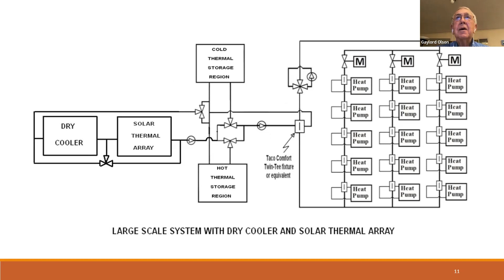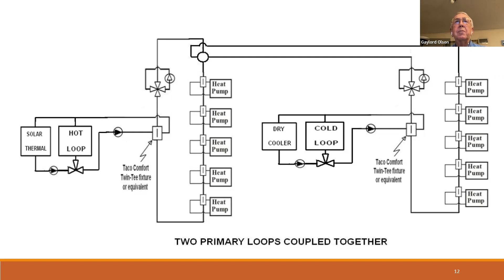This shows only a single path vertically instead of the 3 paths we had before. We're showing the donut fixture coupling the loops together, with hot loop on one side and cold loop on the other, which would work but may not be optimum. It's probably better to have both hot and cold on both primary loops. Okay, next one.